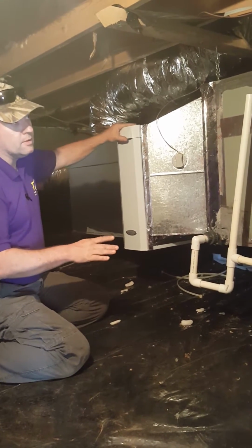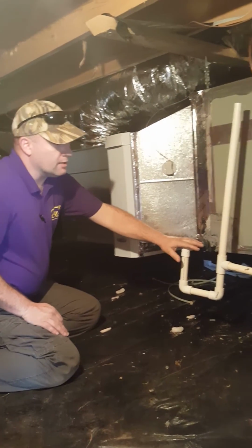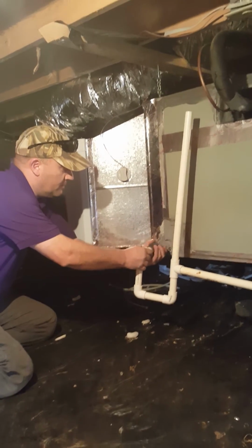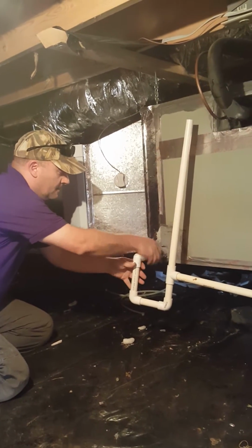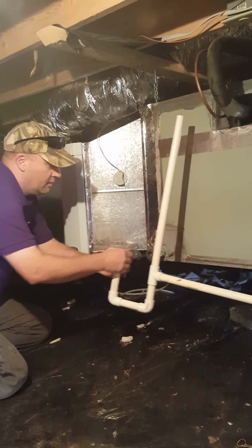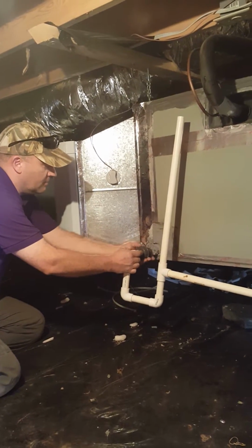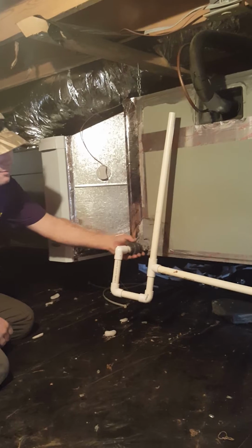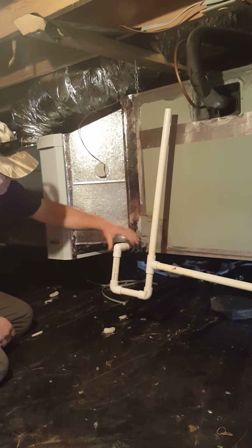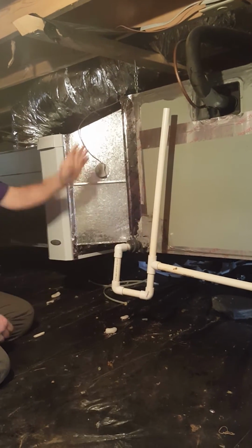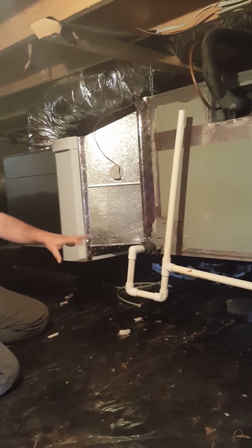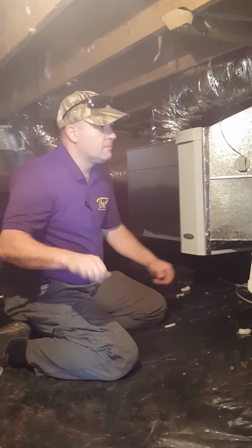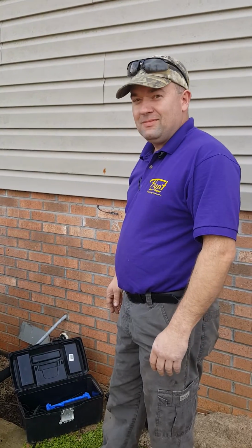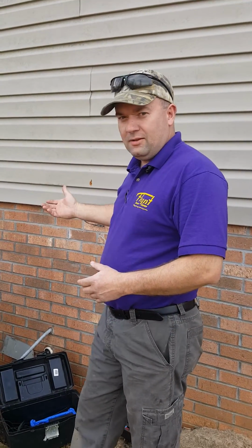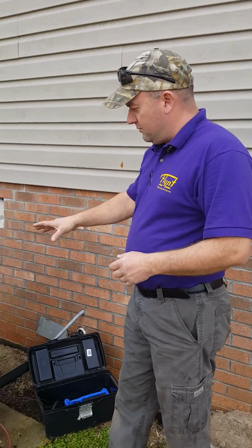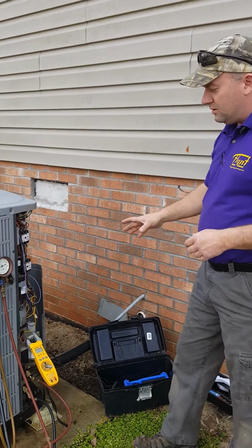The last thing we're going to do while we're underneath the house is the drain line. We're going to disconnect it, use compressed air, blow through it, and clean that drain line up. This unit doesn't have one, but a lot of units will have a condensate pump down here that pumps the moisture out of the system. We will also clean that condensate pump. Alright, so we've checked out the indoor air handler. We've also checked all the capacitors and contactors on the outdoor unit.